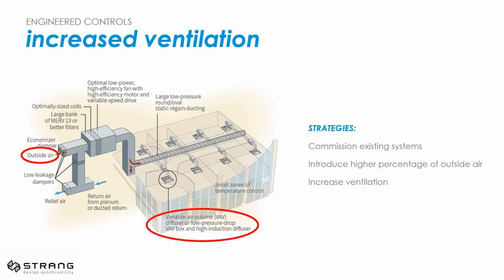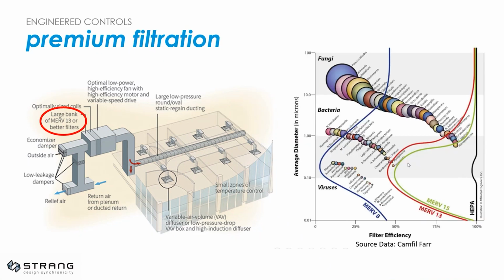You can also increase the ventilation rate, but first review with a qualified HVAC engineer. This is to confirm your existing system is sized to handle the conditioning of the additional outside air. You should also consider upgrading the HVAC system filters to a higher MERV rating if the system's sized to handle them. The diagram on the right of this slide demonstrates how much more effective a MERV 13 filter is in comparison to a more common MERV 8, which one might find in a standard office environment.